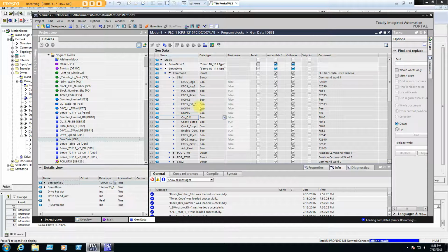Because when you swap them, then if you try to view them, the number will be kind of crazy looking, and so you just want to do it right before you send it. That way you don't have to see it anyplace else, and you make a comment that this is swapping the bytes for the device that you're sending it to. And remember, anything coming back from that device, you need to swap those bytes immediately. As soon as it shows up, you get it into a DB or a memory, whatever you like to use, you swap them immediately. And then that's the data you use.